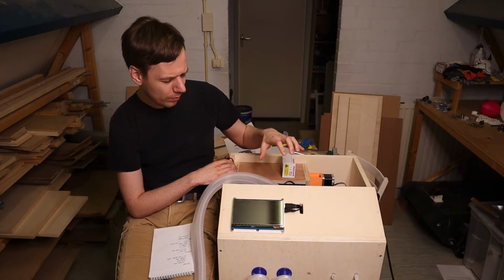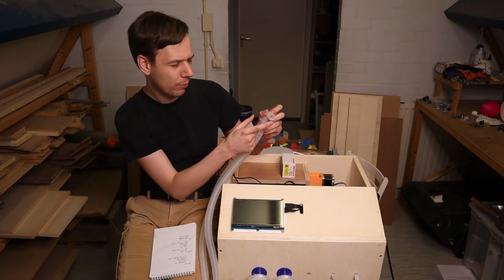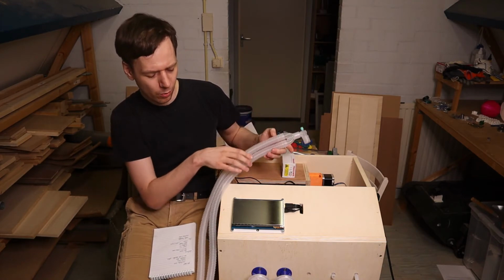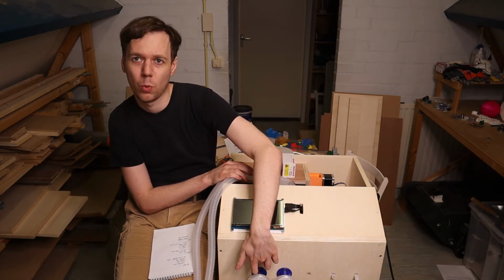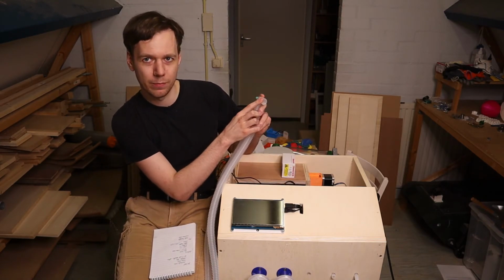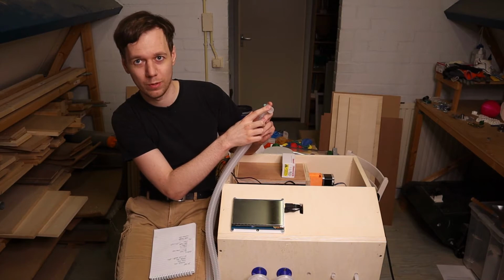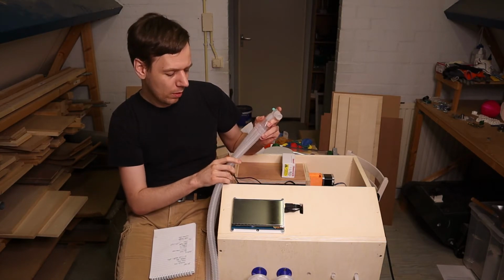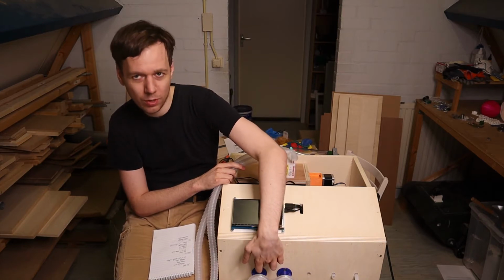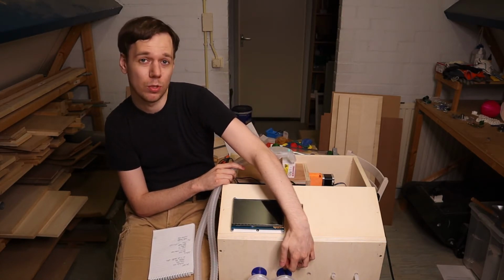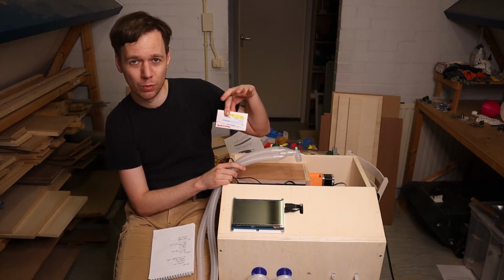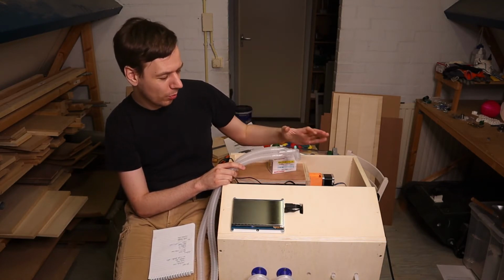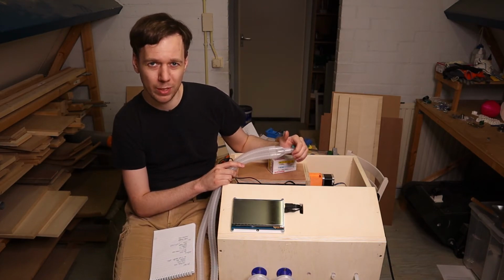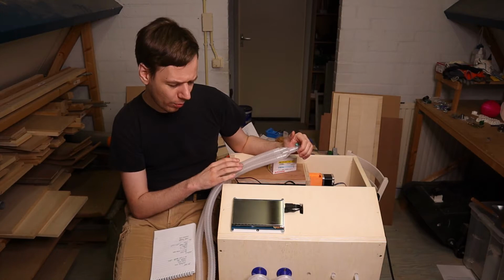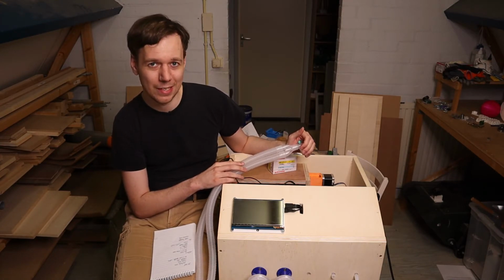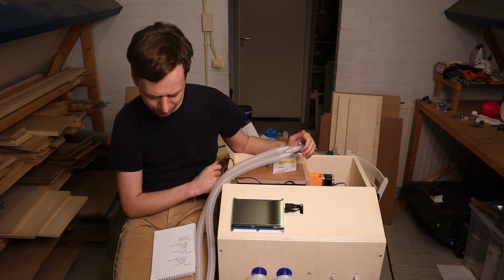But you want either one bidirectional flow sensor here, close to the patient, or you want one on both the inspiratory and the expiratory limb. Now, if you put it here, it's going to get contaminated with COVID and you're going to have to throw it away. The other option, if you put them inside here, you need one on inspiratory and expiratory, so you need two of them. And with flow sensors at 200 a pop, both of those options aren't great. So I'm looking at getting a Venturi-based flow sensor, but currently I haven't yet had any success in getting one of those, but that is still in the cards.